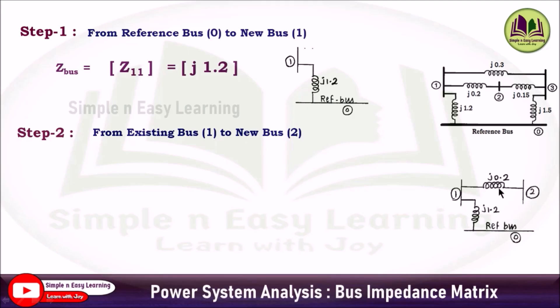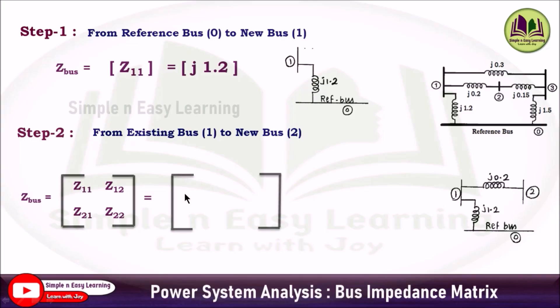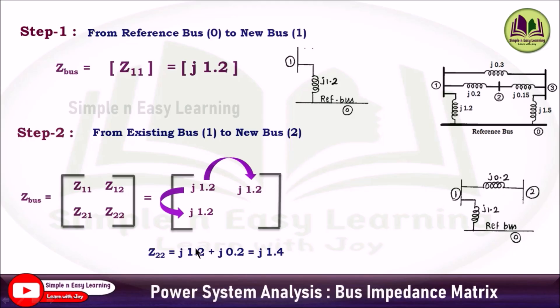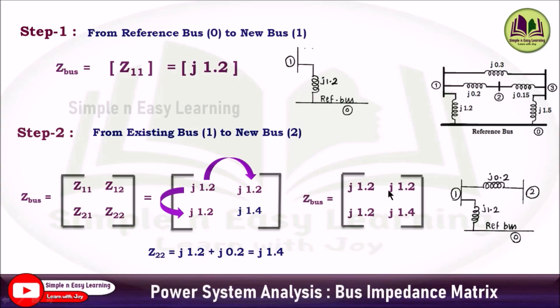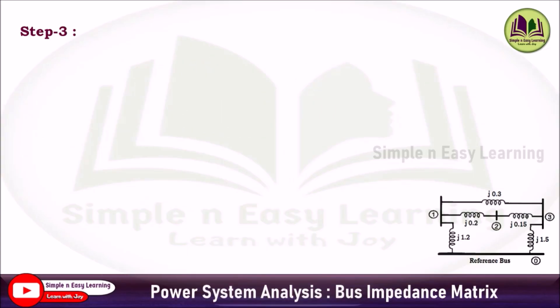Step 2: from existing bus 1 to new bus 2, considering reactance j0.2. Z-bus is of order 2×2 and consists of four terms: Z11, Z12, Z21, and Z22. Z11 is substituted directly from step 1 as j1.2. Z12 and Z21 are obtained by copying Z11, so both equal j1.2. Z22 equals Z11 plus j0.2, which is j1.2 plus j0.2, giving j1.4. So the Z-bus matrix at step 2 is [[j1.2, j1.2], [j1.2, j1.4]].